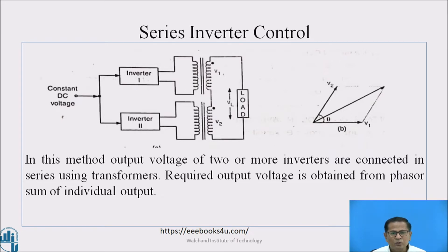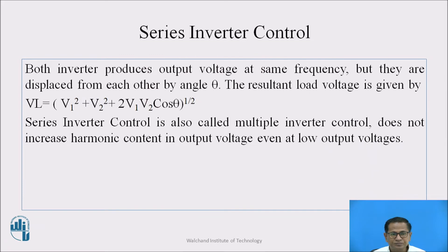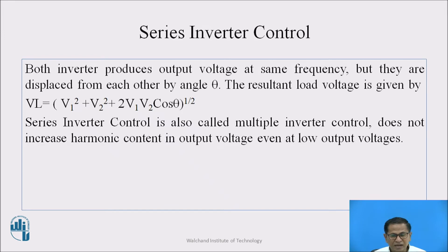In series inverter control, the output voltages of two or more inverters are connected in series with the help of transformers. The required output voltage is obtained from the phasor sum of individual outputs. Both inverters produce output voltage at the same frequency but are displaced from each other by angle theta. The resultant load voltage is given by VL = √(V1² + V2² + 2·V1·V2·cosθ). Series inverter control is also called multiple inverter control and does not increase the harmonic content in the output voltage even at low output voltages.